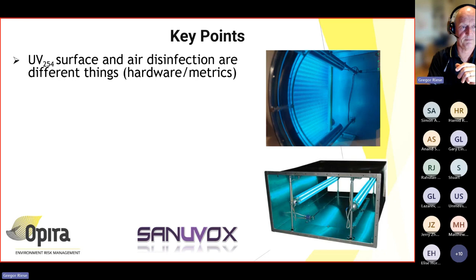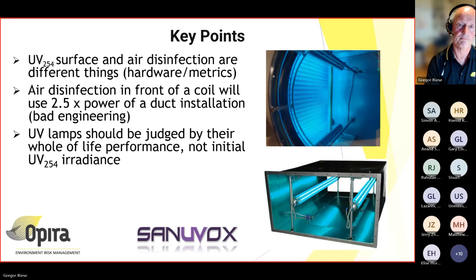On UV lamps: we've had some customers want to compare lamps by initial irradiance. As I said earlier, the very hot lamps have short lives. The Sanuvox lamps don't generate as much irradiance as some of the competition, but they have much longer lives. So you're going in there every 2 years, with a 25% decline, instead of replacing lamps every year with a 50% decline.